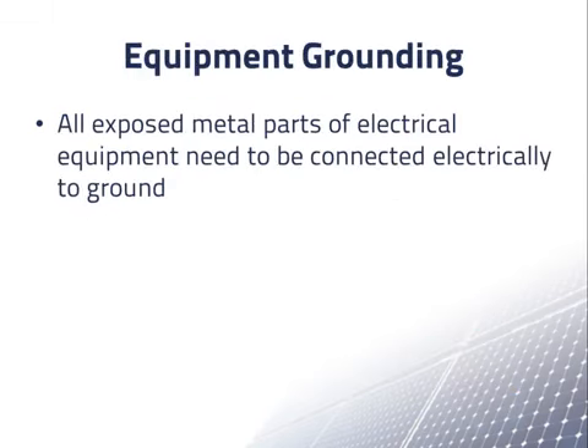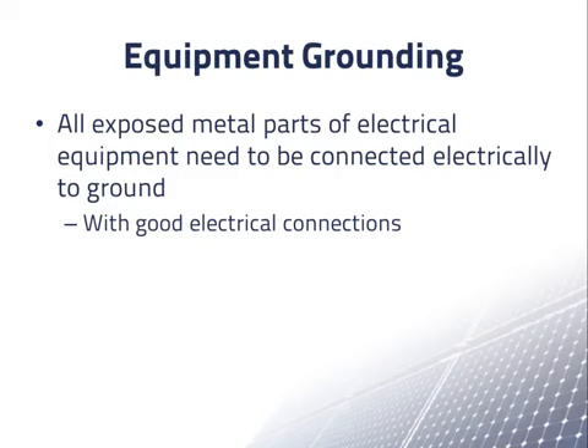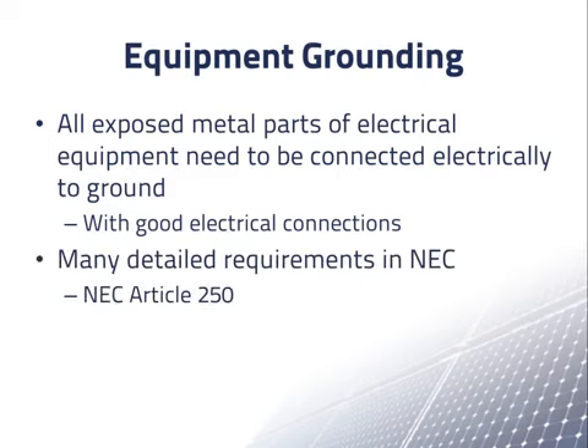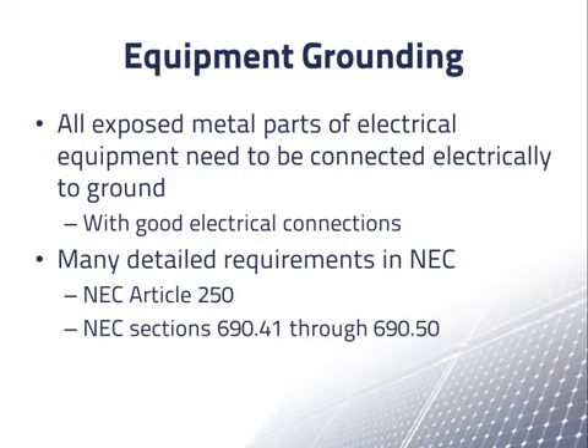So repeating, all exposed metal parts of electrical equipment need to be connected electrically to ground. And of course, these connections need to be good electrical connections. The detailed general requirements for grounding are in NEC Article 250, which has over 100 sections. Also, additional requirements for equipment grounding in PV systems are found in NEC Section 690.41 through 690.50. In this presentation, we'll only be able to discuss some of the main points of equipment grounding in PV systems.